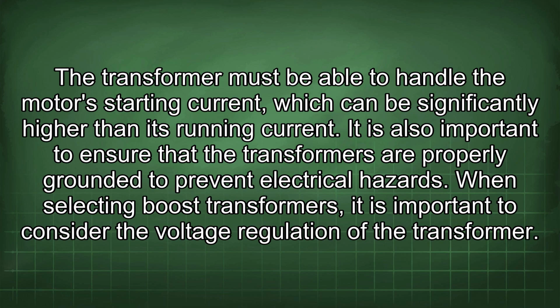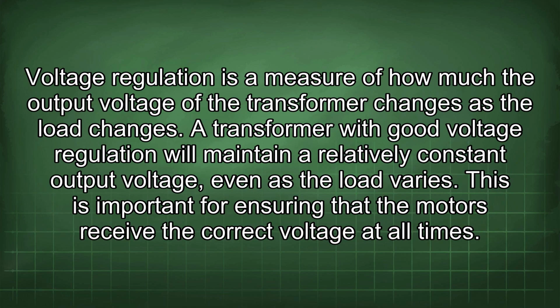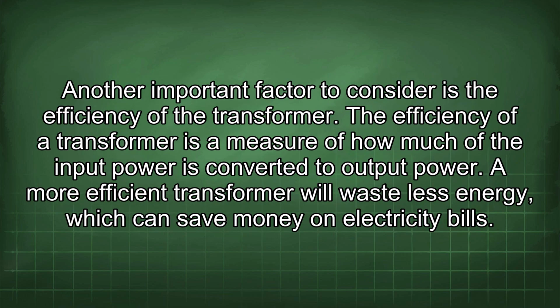When selecting boost transformers, it is important to consider the voltage regulation of the transformer. Voltage regulation is a measure of how much the output voltage of the transformer changes as the load changes. A transformer with good voltage regulation will maintain a relatively constant output voltage even as the load varies. This is important for ensuring that the motors receive the correct voltage at all times. Another important factor to consider is the efficiency of the transformer. The efficiency of a transformer is a measure of how much of the input power is converted to output power. A more efficient transformer will waste less energy, which can save money on electricity bills.